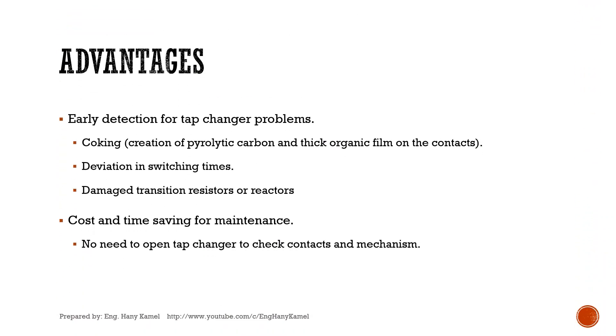The advantages of this test include early detection of tap changer problems like coking, which is the creation of pyrolytic carbon and thick organic film on the contacts; deviation in switching times; and damaged transition resistors or reactors. It also provides cost and time savings for maintenance, as there is no need to open the tap changer to check contacts and mechanism.